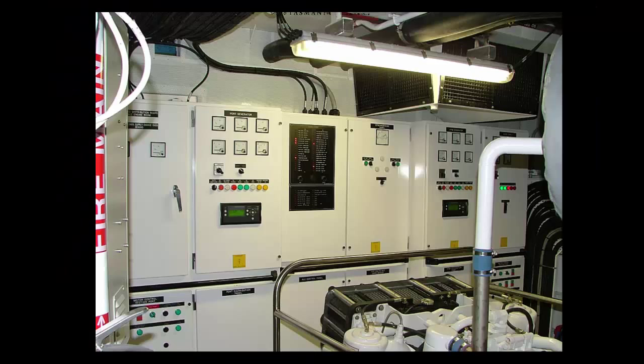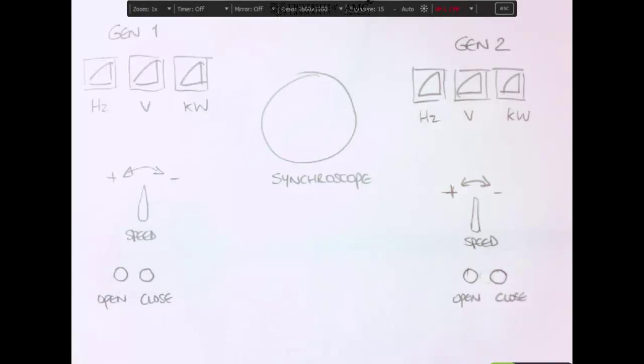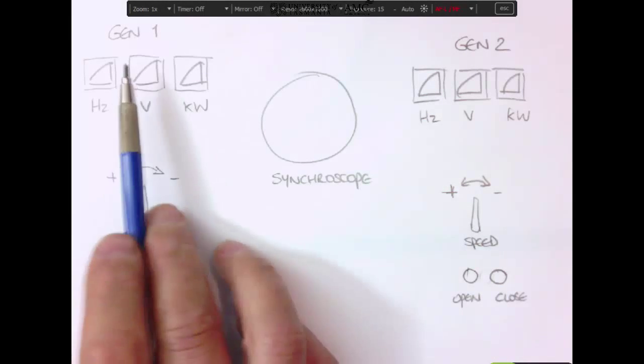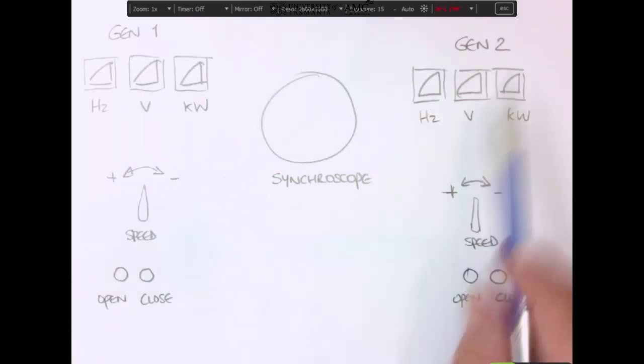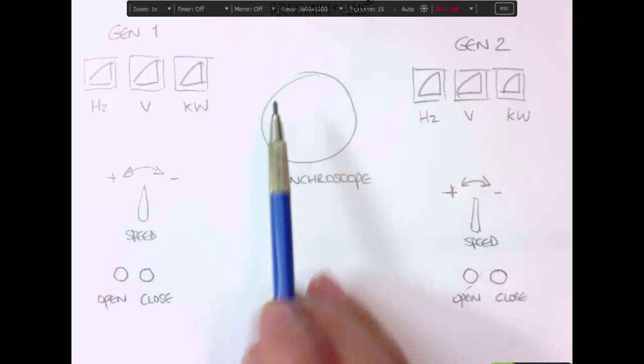Okay, so what does that look like? Well, this is a typical kind of setup that we might see. Here's one alternator or one genset, there'll be another one over here, and here we've got the port generator, and this is the board for the port generator. Here's the one for the starboard generator, and right in the middle we have a synchronization panel. So when we parallel, we can have both the port and starboard generator on at the same time. Here's roughly the panels we were looking at in that picture. We've got generator 1 here, panel here, generator 2, panel here, and we've got a synchroscope in the middle.